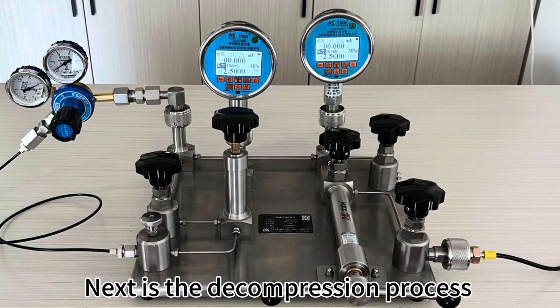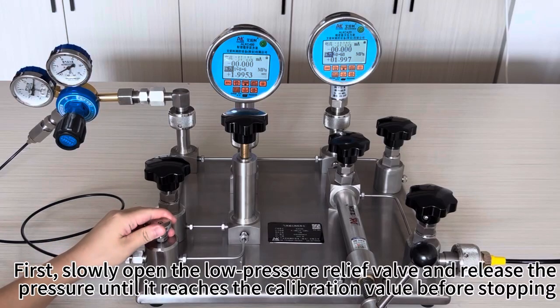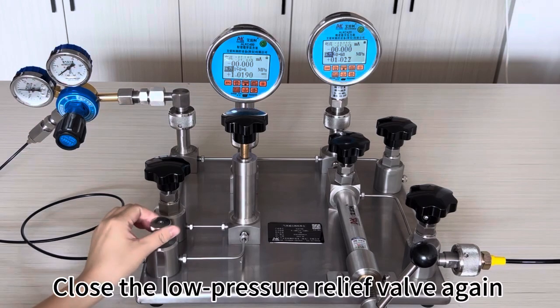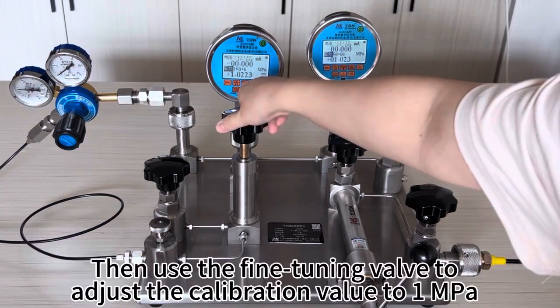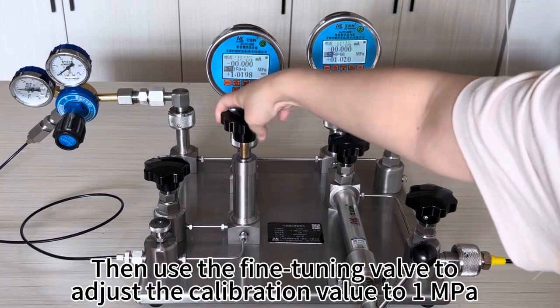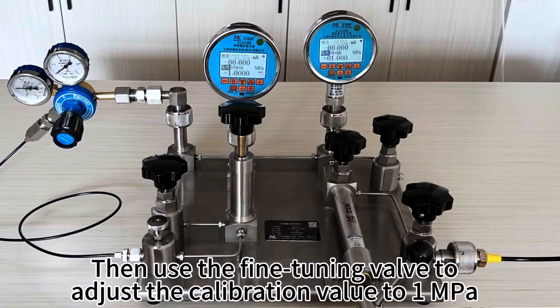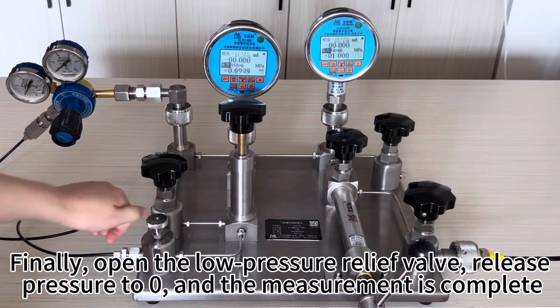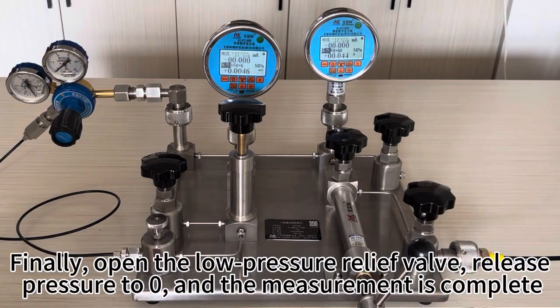Next is the decompression process. First, slowly open the low-pressure relief valve and release the pressure until it reaches the calibration value before stopping. Close the low-pressure relief valve again. Then use the fine-tuning valve to adjust the calibration value to 1 MPa. Finally, open the low-pressure relief valve, release pressure to 0, and the measurement is complete.